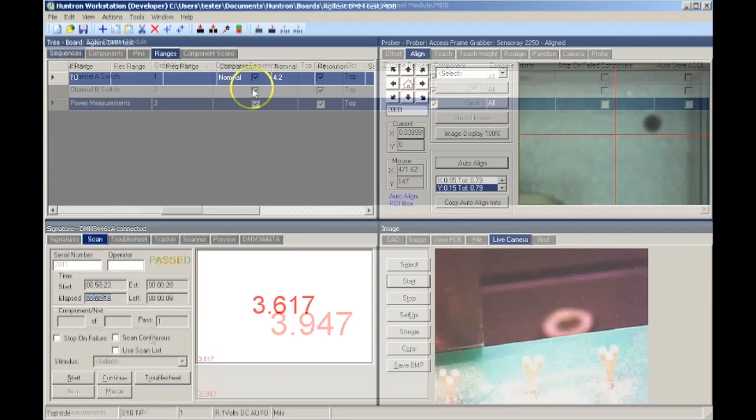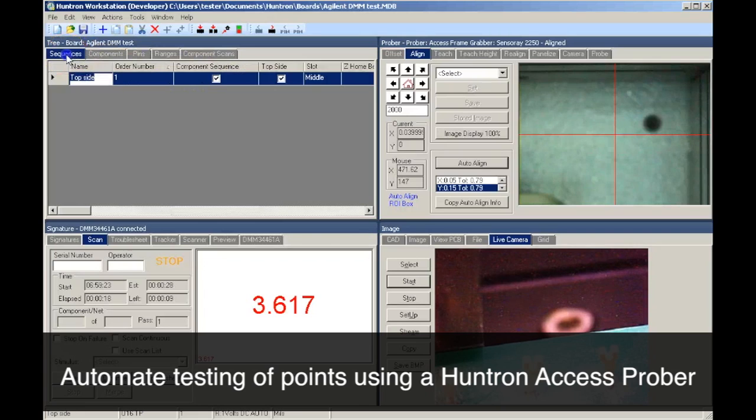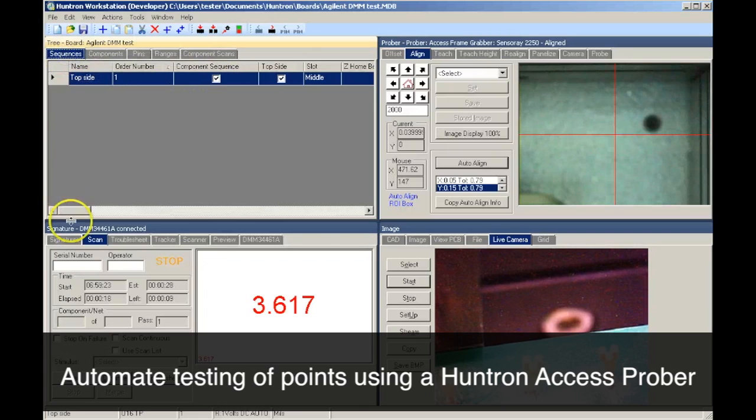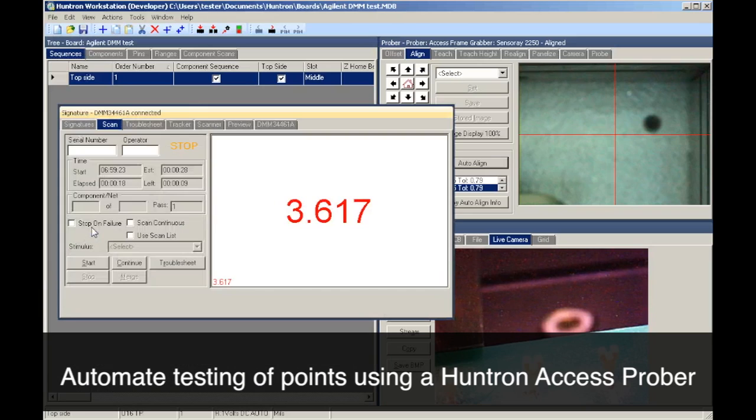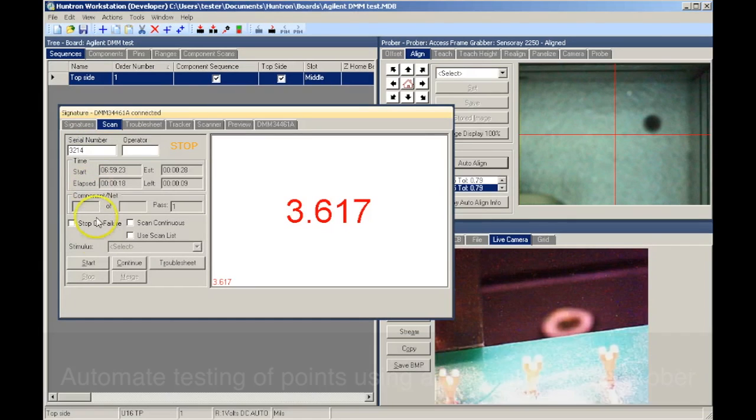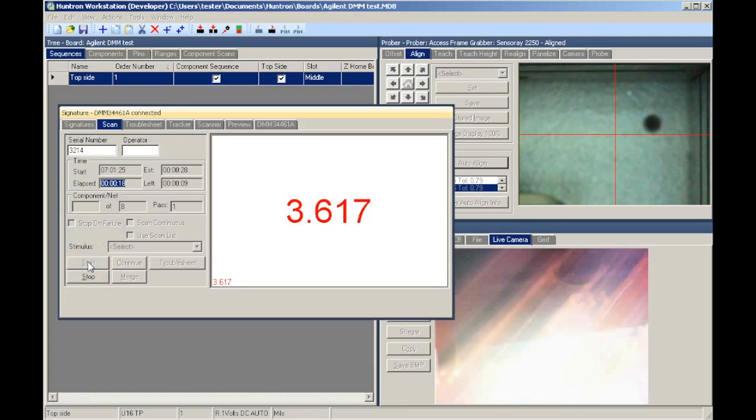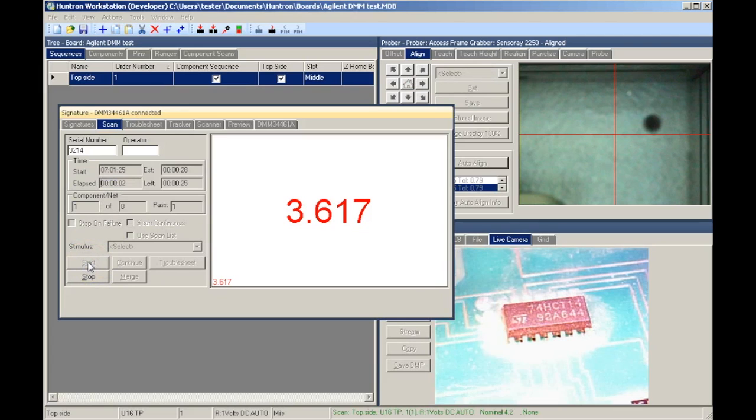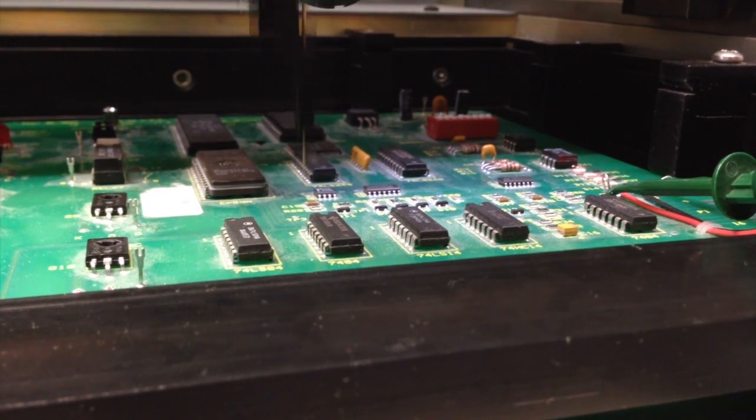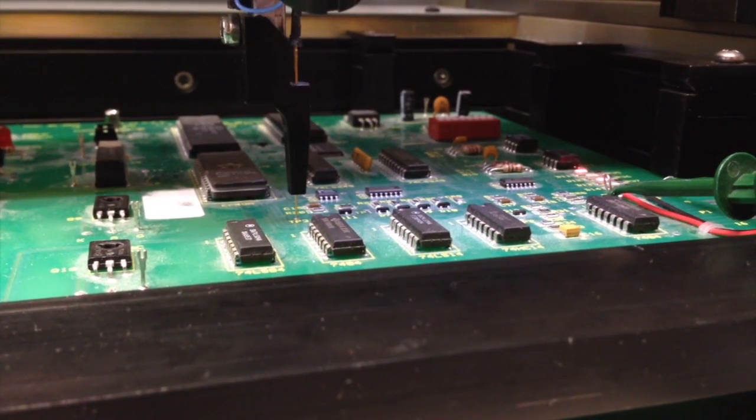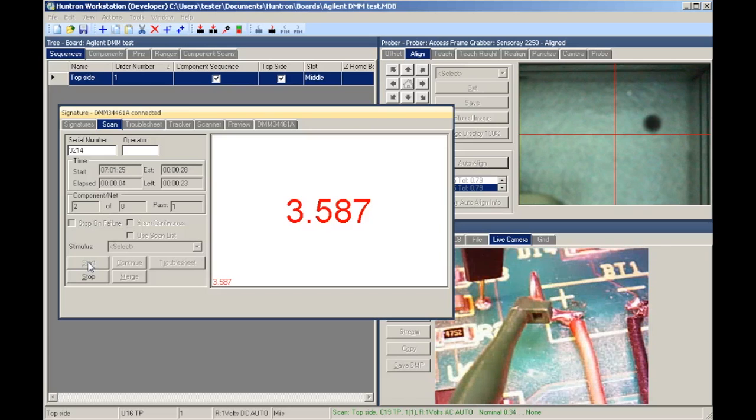The other method of interfacing to the test points is using a Huntron Access Prober. Once the database of test points is created, the PCB to test is mounted in the Access Prober and the location of each test point is stored in the software using the Access Prober camera. Once the locations are taught, the test can be executed and the Prober will place the test probe on each point to obtain the desired measurement.